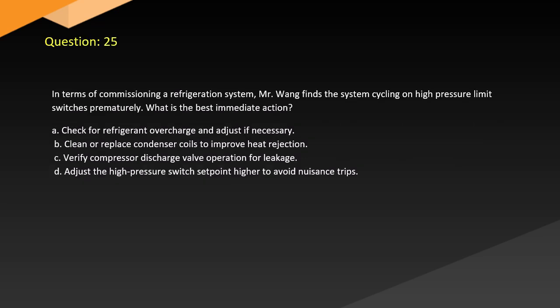Question 25. In terms of commissioning a refrigeration system, Mr. Wang finds the system cycling on high-pressure limit switches prematurely. What is the best immediate action? A. Check for refrigerant overcharge and adjust if necessary. B. Clean or replace condenser coils to improve heat rejection. C. Verify compressor discharge valve operation for leakage. D. Adjust the high-pressure switch setpoint higher to avoid nuisance trips.